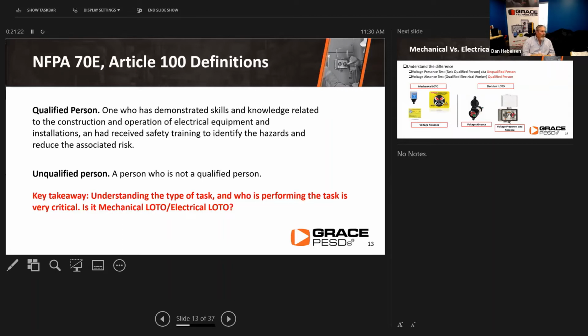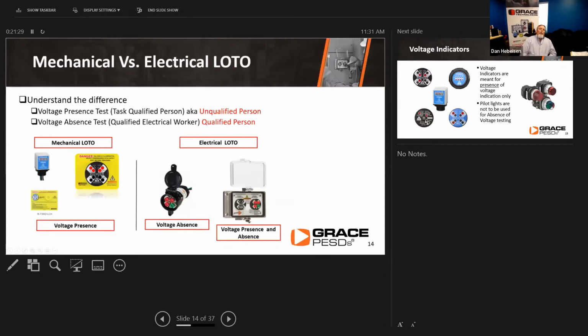And then verifying, is this a mechanical lockout tagout or electrical? So understanding the difference. So a voltage presence test for a task qualified person is also considered for an unqualified person. There are devices out there that are created to give you the opportunity to see that the voltage is present, and that's going to give you a visual indication of some type. And then when you go into your electrical lockout tagout, there are devices that give you the opportunity to use your meter and do your live, dead, live test to prove out the voltage absence. And also you've got a combination package of products that give you the visual presence and absence accordingly. And we'll talk about these a little bit now.